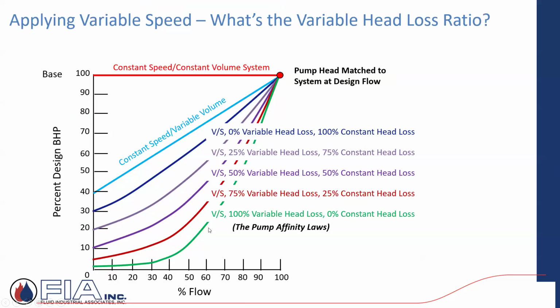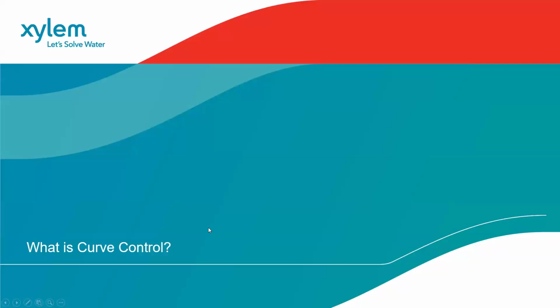This is just showing you the variable head loss ratio, depending upon constant head loss versus variable head loss. Sometimes we'll get into some examples, but that's the control head. Because in the mechanical room, it's going to read a different constant head loss versus if I'm remote out in the building. And how that impacts what the variable head loss will be depends upon where that constant head loss is. And it's all a function of the pump affinity laws.